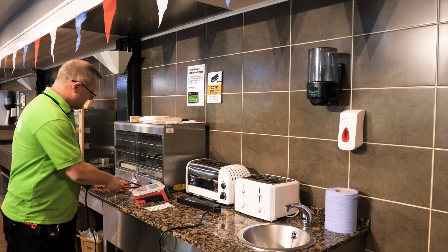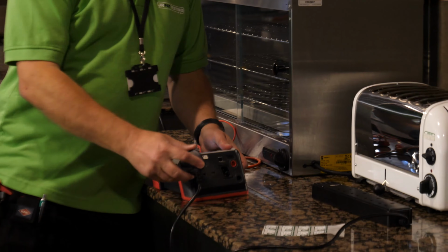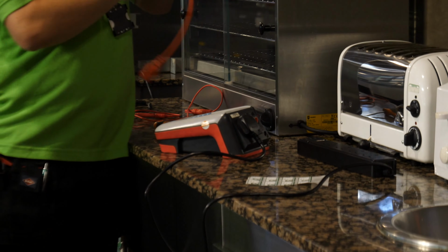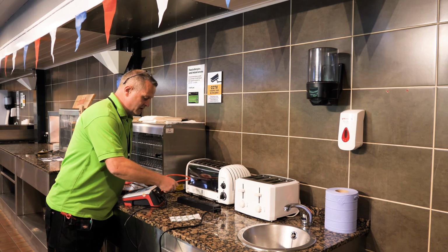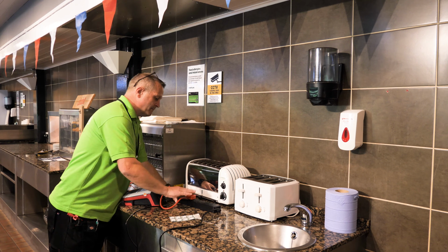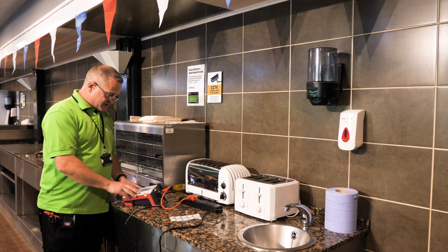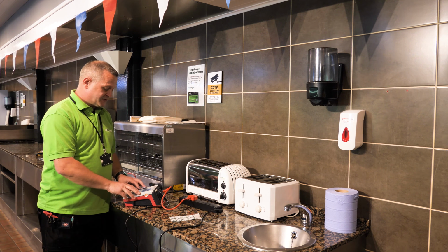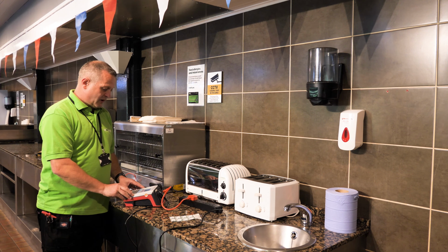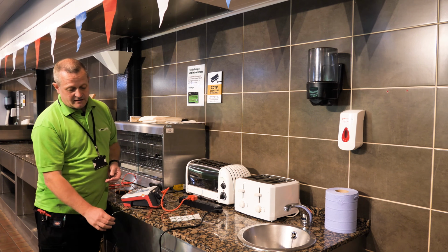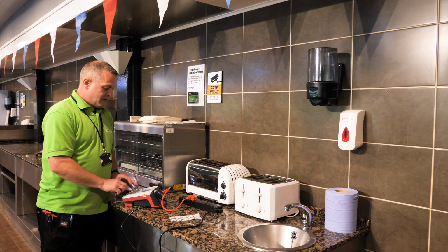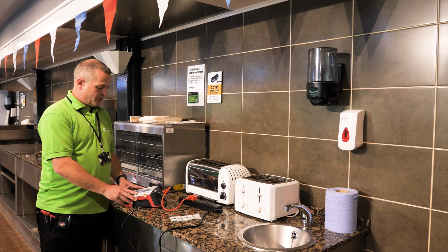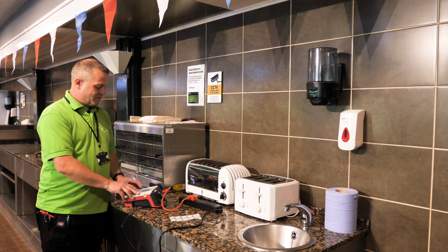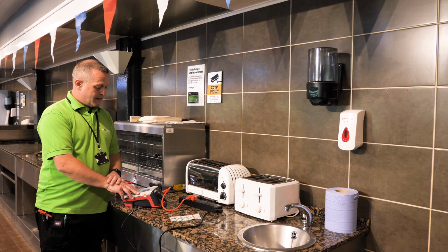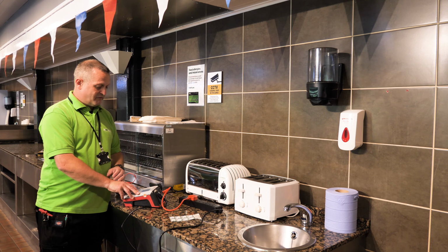So then to conduct the test we're going to use an IEC lead, so we're going to plug the extension lead into the PAT tester, and then using an IEC lead we're going to test the extension lead. So this particular PAT tester has already got a pre-programmed test for an extension lead, and all I have to do is choose the program with the correct lead length. So on this occasion it's up to a 6 meter lead, and then it's effectively a class 1 appliance that it will go through, ticking all the boxes to say everything's in order, we'll conduct the IEC lead test, the earth continuity, the insulation, and then finally it'll conduct a polarity test. And they've all passed.